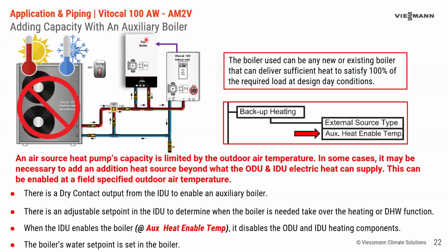And remember, it's probably also doing domestic hot water. So you're going to have that boiler water hot enough to do the hottest load, either building heat or domestic hot water. And that's a number that you're going to set. And you're probably not going to use a heating curve in this boiler because it's only being enabled when it's cold outside. So you're probably just going to run a fixed set point, but you have to determine that set point based on what you're going to supply heat to.